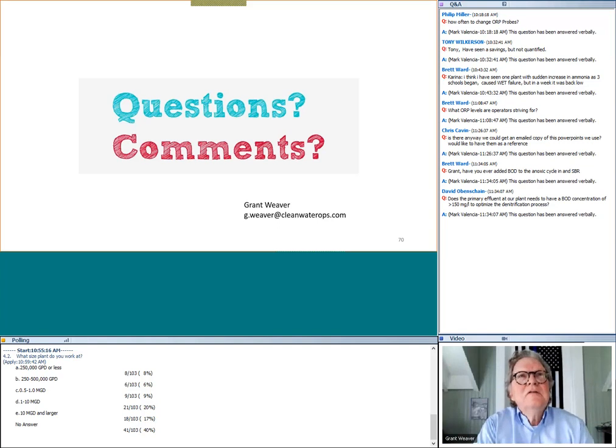My guess is you need probably that 160 kind of number that Karina mentioned. It's probably a pretty good minimum for nice, consistent removal. Now, there's ways to supplement that. When we get into phosphorus removal, I'm actually going to talk about recycling some waste sludge back into the system. So if you can bring a little bit of digested sludge in, maybe you're going to bring some soluble BOD in as it breaks down.